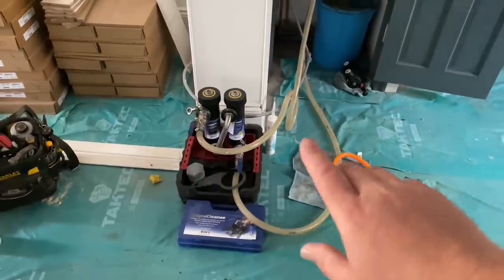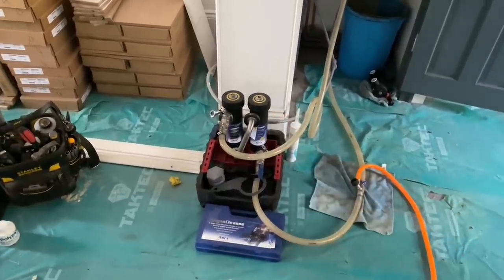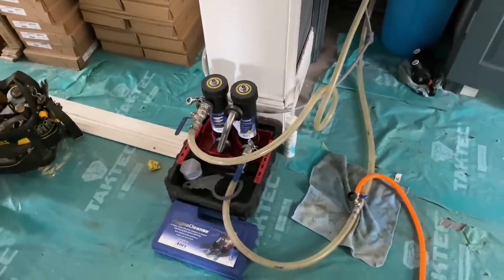Right, so this has been on now for about 2 days, running the heating up again. I'm just going to give it a last blast through now and then get it flushed out and then get the protector into it. So at the minute, we're just going to run it up to temperature, much to the disgust of the painters because they're absolutely boiling. Get it up to temperature and then give it a flush through, completely flush the system, refill it, and pop the inhibitor in, and then complete, and then shut it down, then completely seal it up, and away we go.